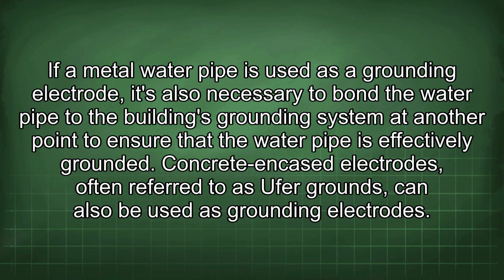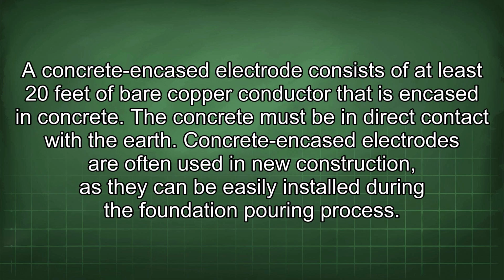Concrete encased electrodes, often referred to as Ufer grounds, can also be used as grounding electrodes. A concrete encased electrode consists of at least 20 feet of bare copper conductor that is encased in concrete. The concrete must be in direct contact with the earth. Concrete encased electrodes are often used in new construction, as they can be easily installed during the foundation pouring process.